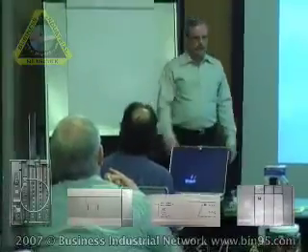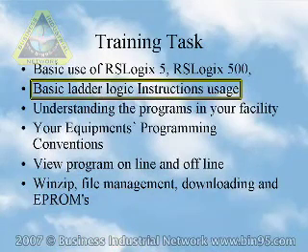When they designed the hardware system for the PLC 5, they designed it on an octal-type address — they don't use eights and nines in the numbering system. When they developed the SLC 500, they figured out that's difficult for humans to work with an octal system, so they moved to a decimal system. We'll go over basic ladder logic usage and the most common instructions, as I mentioned before.